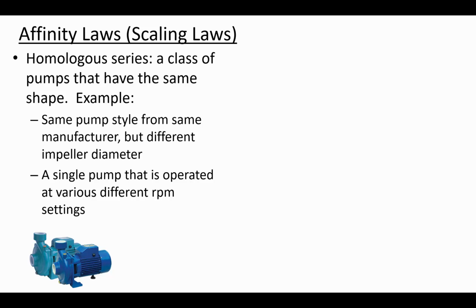Remember what we looked at on Monday and Friday of last week: you combine pumps with the system curve to find the operating point. So what flow rate you're going to get out of a pump depends on how much work the pump is doing and what force it's working against — how high it has to lift the water, and what the frictional losses in the system are that the pump is trying to overcome. So how much effort it has to do kind of reduces the flow rate, the more and more cutoff head that it has.